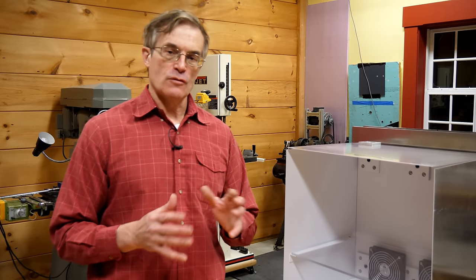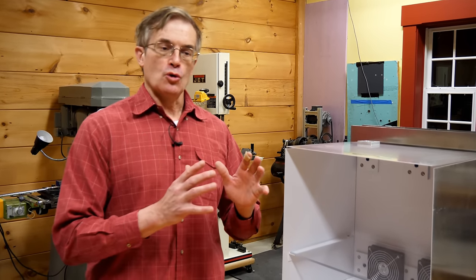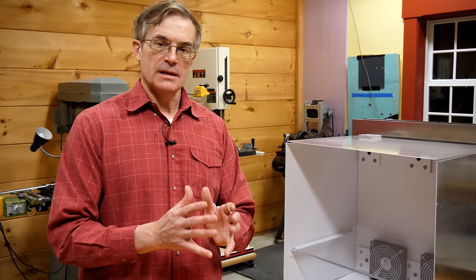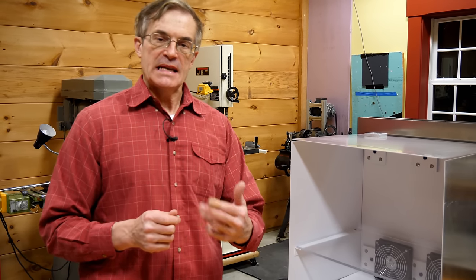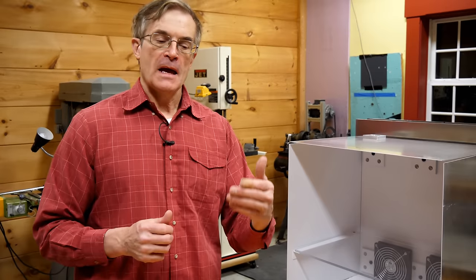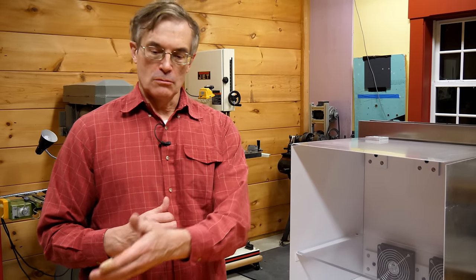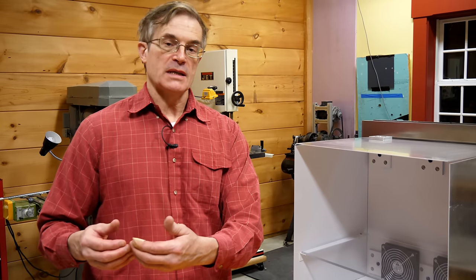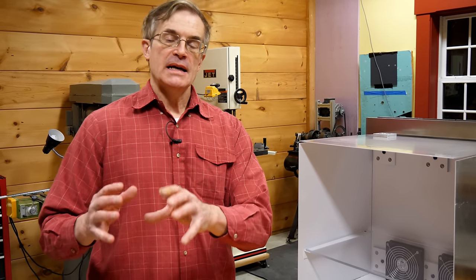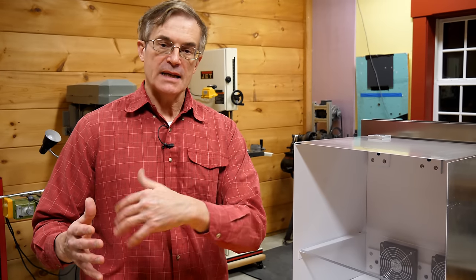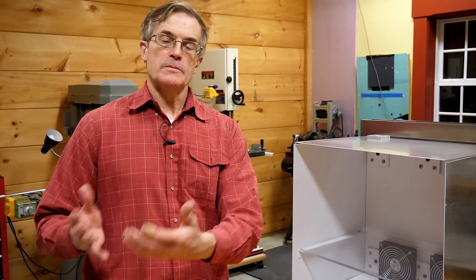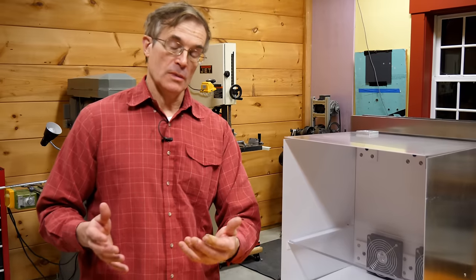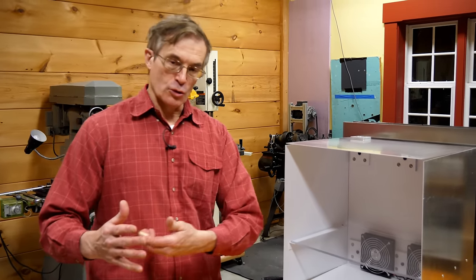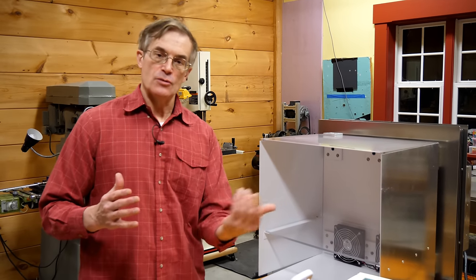In a typical phase change refrigerator, a compressor will compress a gas such as a fluorinated hydrocarbon like freon, and it will turn it into a liquid and produce a very hot liquid. That liquid then will transfer its heat through a heat exchanger into the atmosphere, and then that relatively cooler liquid will move over to an expander where it's allowed to once again change phase back to a gas. That cold gas then travels through a secondary heat exchanger where it absorbs heat from a refrigerator or from a room, and then that relatively warmer gas will return back to the compressor to continue the cycle.